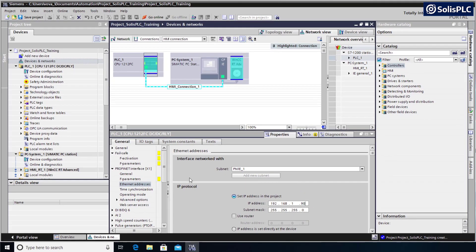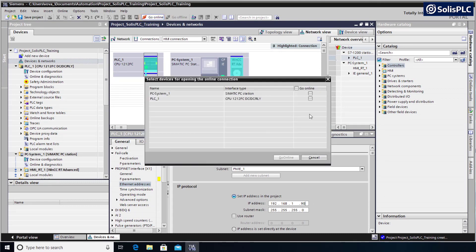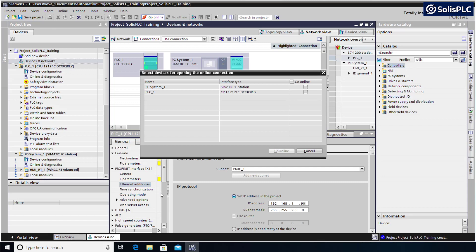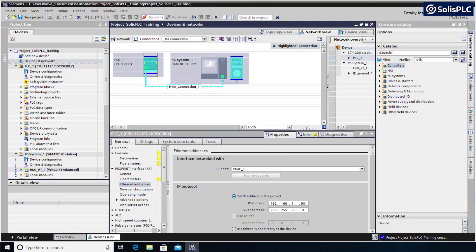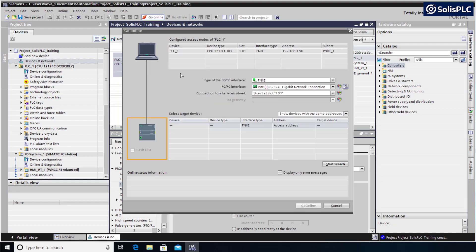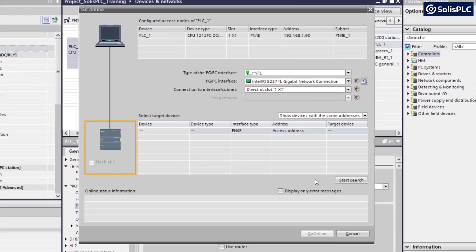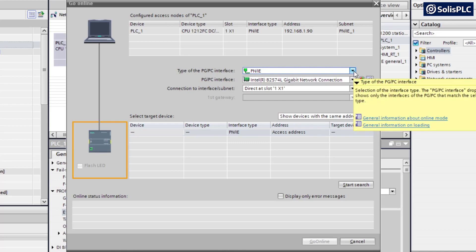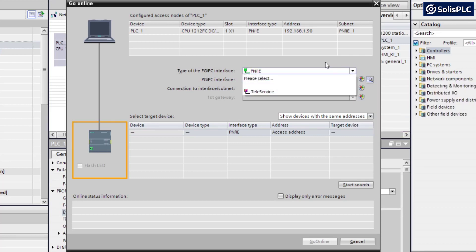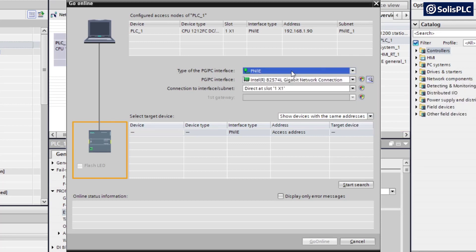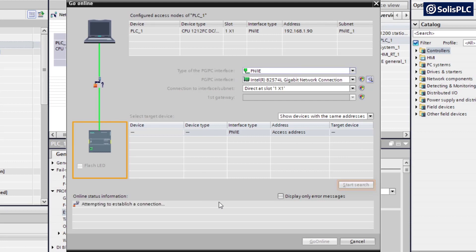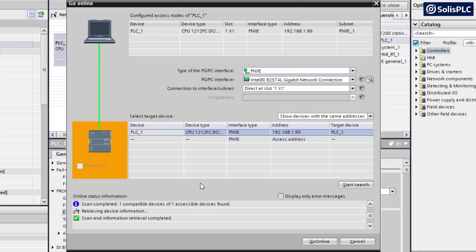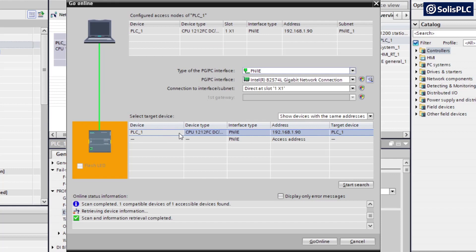We're going to attempt to connect. I'm going to press this Go Online button. We should definitely get some errors because we are certainly not configured properly for the safety PLC, but we should still be able to go online and connect to the physical device. Once the Go Online menu is up, we can select the interface that's going to be perhaps different depending if you're using a laptop, a desktop, or if you have multiple ports on your device. We need to press this Start Search button, which is going to attempt to connect to the IP address that we have specified in our configuration.